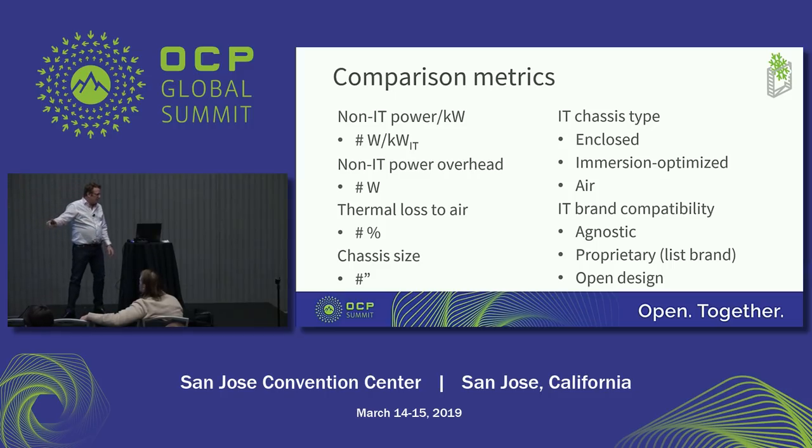Last one on comparison metrics. Some of the information that is also relevant for comparison is non-IT power per kilowatt. If you require pumps to displace the liquids, don't forget these pumps consume power. You need to be aware of that in the total efficiency calculations. The power of a pump is easiest to relate to a power per kilowatt of IT.